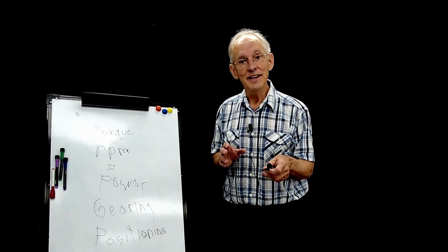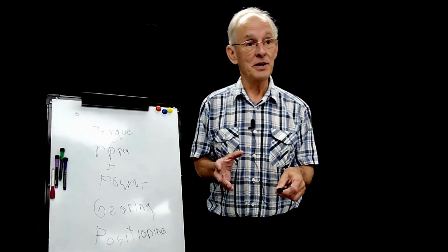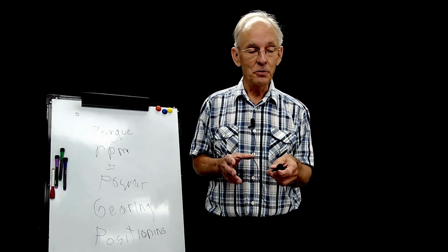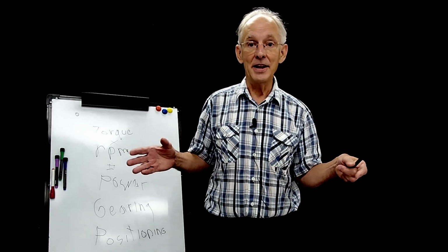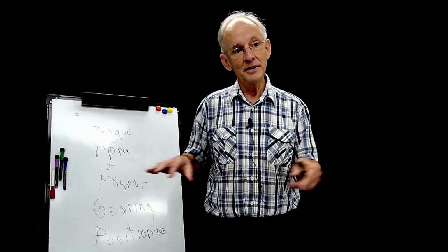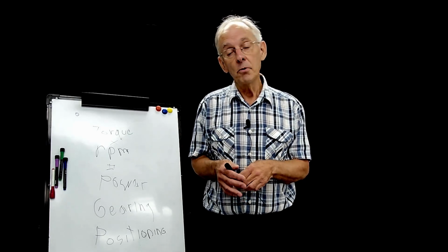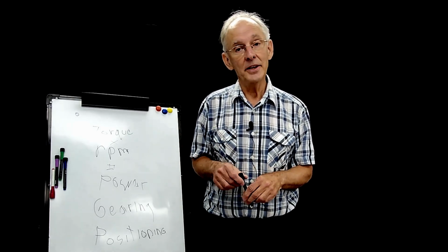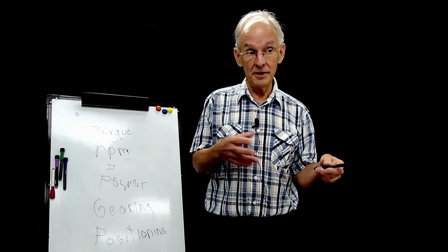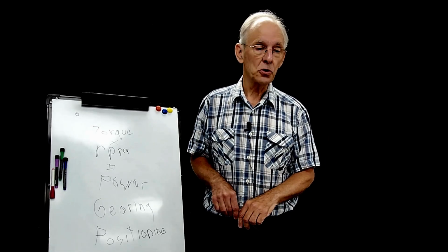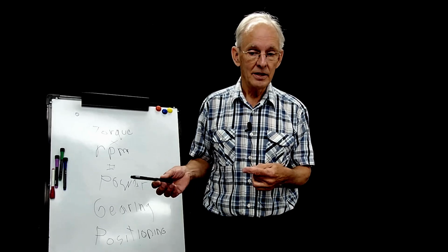Air over meaning it was intended to be in an airstream to cool it. And that airstream was provided by the fan. They mounted the motor in part of the airstream. When the cover was on, the motor didn't get very warm. You could hold your hand on it. But when the cover was off, it got up to that high temperature. Now, of course, the heat is going into the load.